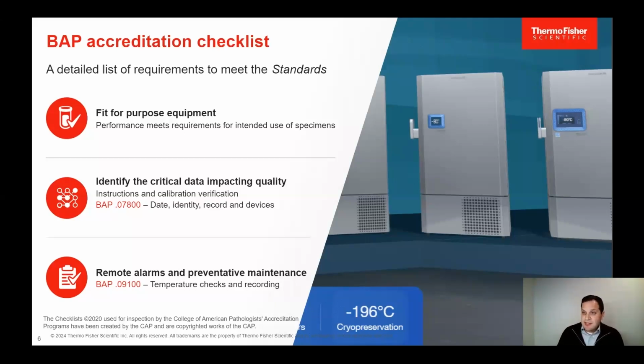So users should really understand the options that will best remain with reliable temperature performance. One of the clauses I listed to identify the critical data impacting quality is 07800. When we're talking about storage equipment, calibration, and calibration verification, what it's asking is that you include the date the calibration was performed, the identity of who ran the calibration, records of the results, as well as the device that was used against calibration or the instrument to be calibrated. All this is part of the evidence of compliance. The second clause I'm pointing out is remote alarms and preventive maintenance. This is when temperatures are being checked and recorded on each day of use, and it's specifying which unit and location for all the temperature-dependent instruments and equipment. Again, these are just 2 of the 178 clauses in that checklist. If you'd like more information, I've cited the checklist as well as the manual in my slides.